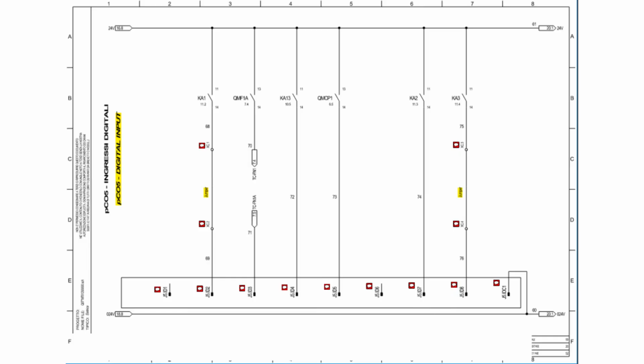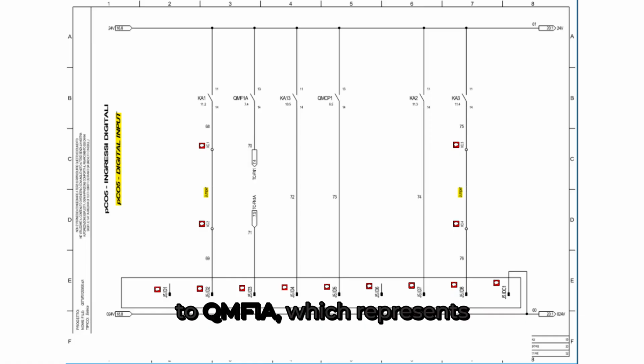is satisfied. The second column connects to QMF1A, which represents the magnetic circuit breaker feedback for fan 1A. This input confirms whether the fan's breaker is in the on position. When the breaker trips or is manually opened, the input goes low, and the controller recognizes a fault condition.